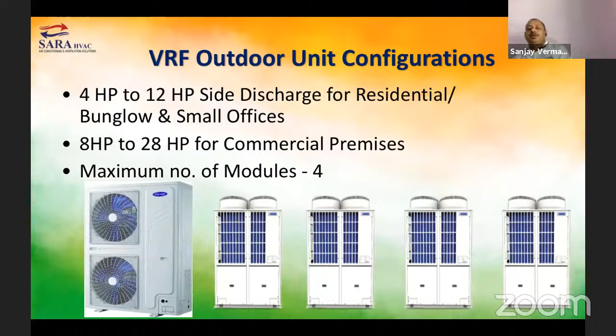...to 28 HP for commercial premises. It differs from manufacturer to manufacturer. Some manufacturers offer 8 HP to 24 HP in a single outdoor machine, a few go up to 26 HP for commercial premises, and one other Indian multinational company offers up to 28 HP for commercial premises - that being a single module of outdoor VRF system. We can add 4 modules together to get the maximum capacity, meaning 28 HP maximum capacity available in the market multiplied by 4. So this much a single machine can be used for bigger commercial premises.